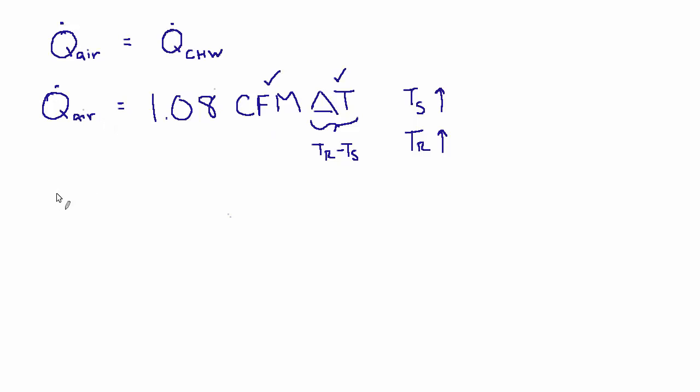So now that's the air side. Let's look at what's happening on the chilled water side. So again, the heat load is the same. And our rule of thumb equation for heat load on the water side is 500 GPM delta T.